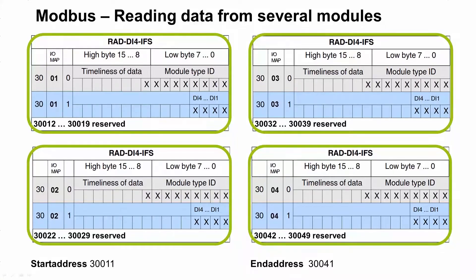If several I/O modules are to be read by a controller, it should be noted that each I/O module uses 10 words. Therefore, a range of Modbus addresses can be read. For example, the process data of four I/O modules of the same type with I/O map addresses 01, 02, 03, and 04 can be read in one request. In this case, an address area with 40 words — Modbus register addresses 11 to 41 — can be read.